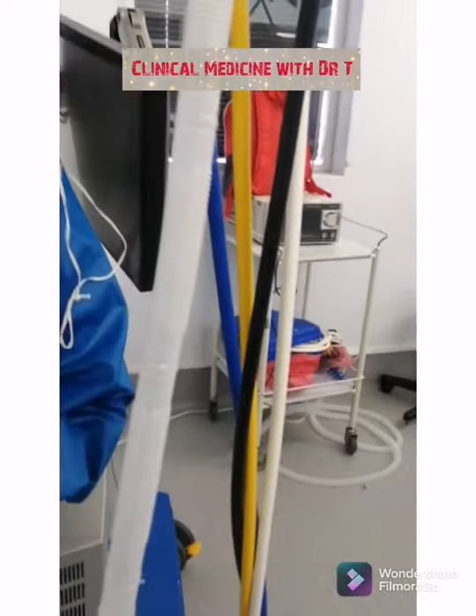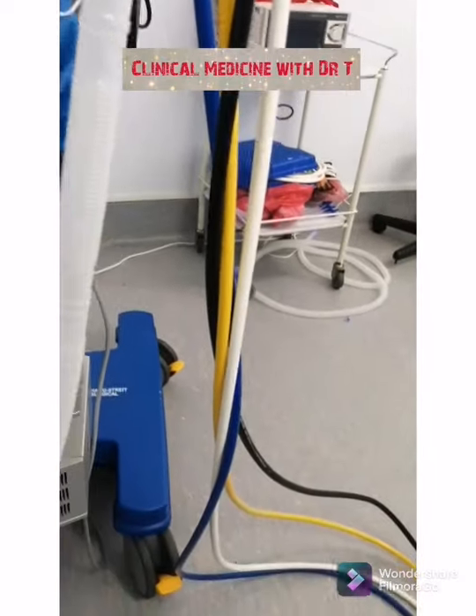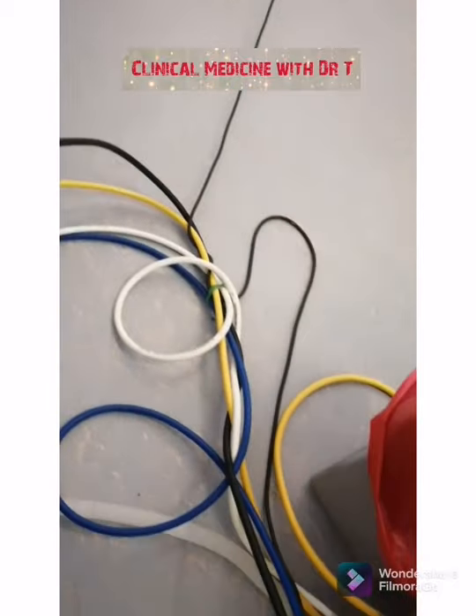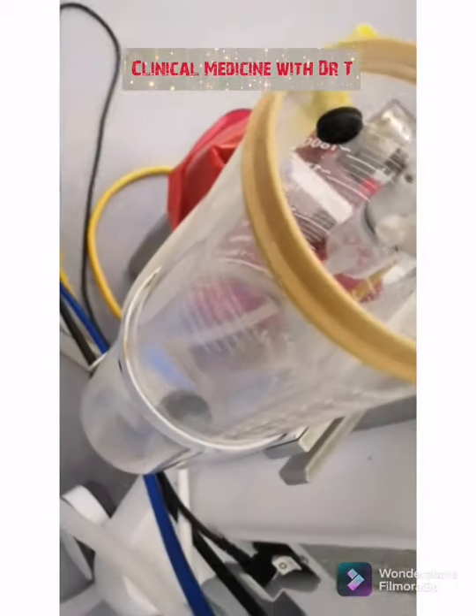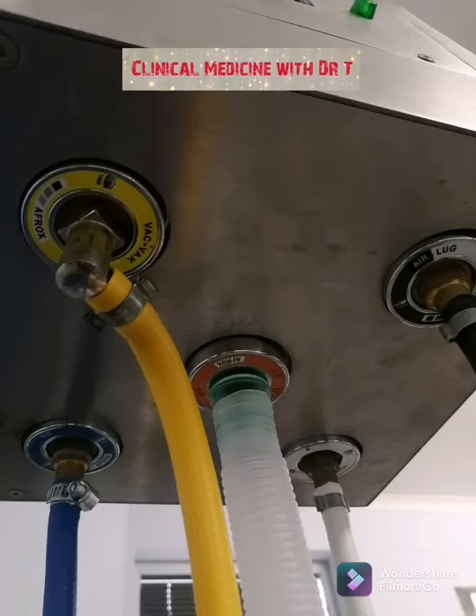So we're going to start with the pipes. So the pipes that you are seeing right now: the blue pipe, the smooth blue pipe, that's nitrous. And the white pipe, the plain white pipe, that's oxygen.